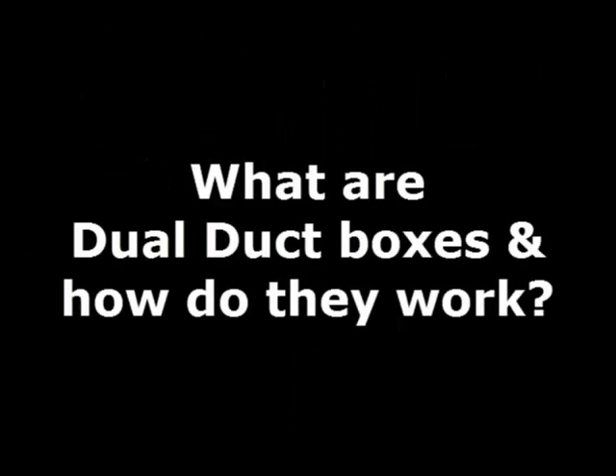I'm Jenny Civey and today we're going to talk about dual duct boxes and how they work. We've already discussed single duct and fan powered boxes. The last major type of box is the dual duct box. Dual duct boxes probably aren't as popular as single duct and fan boxes, but you'll run into them every now and then. Like all boxes, dual duct boxes have a discharge that's ducted out to the diffusers in the space.